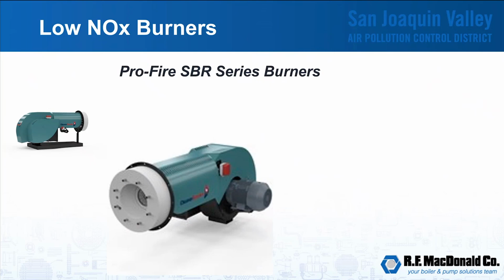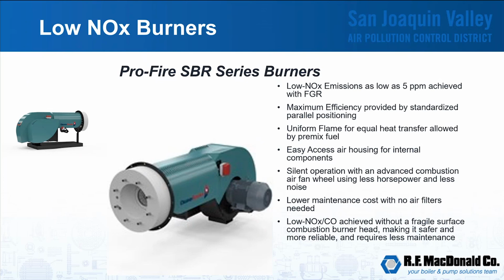Next, we have our ProFire SBR series burners. These are our jet-style burners that are made to fit on any boiler out there. These units utilize FGR and can get down to 5 ppm with no problem. They maximize efficiency by using parallel positioning as standard and give you equal heat transfer across your unit.